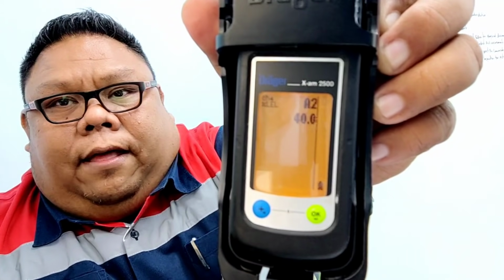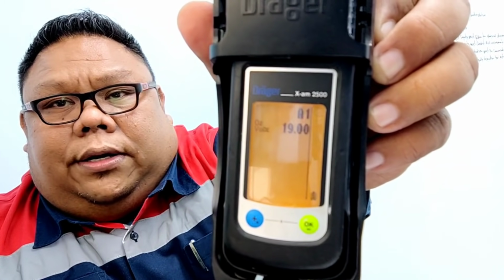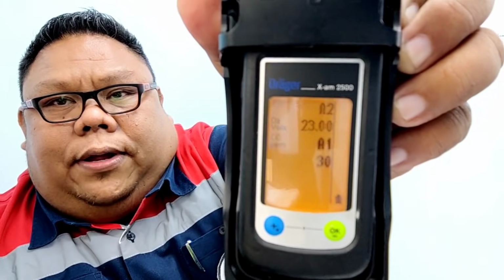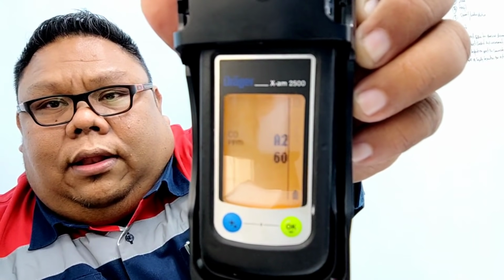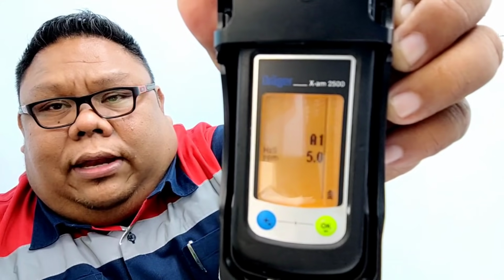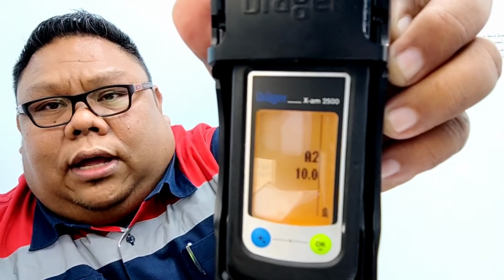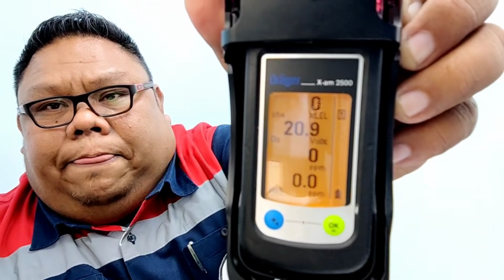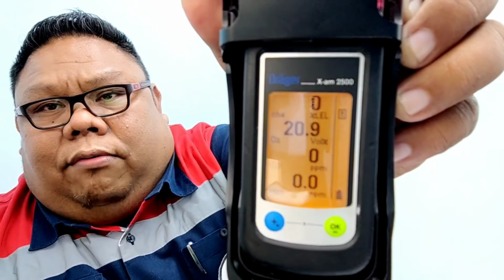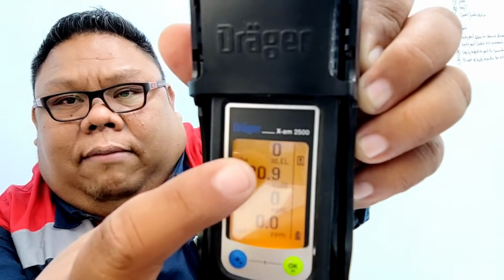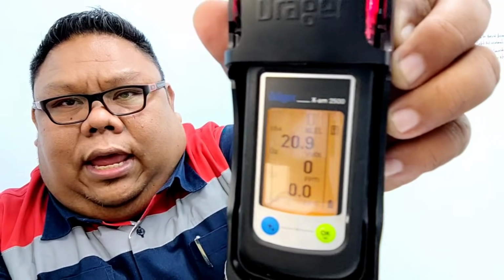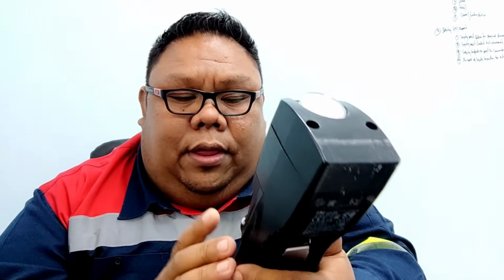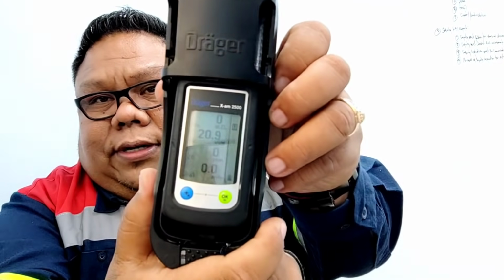It will show how much it senses against the standard. After that, the unit itself will provide the LEL standard and also the carbon standard, and it will go to the normal range. The beacon lighting up means it's sensing fumes, or that the sensors are sensing the fumes, or the pump—see, the pumps are running now.